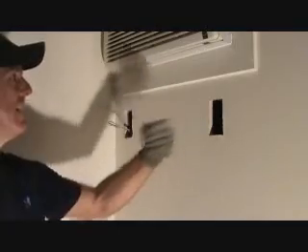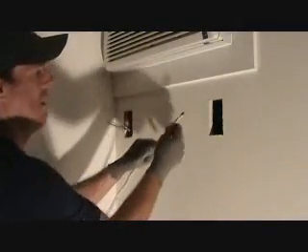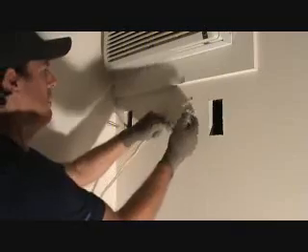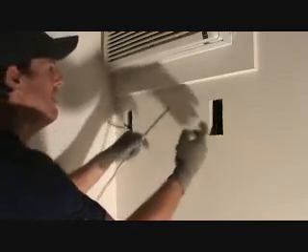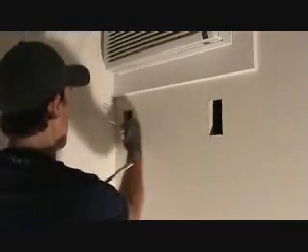So that means we got to put one wire through here and out. Then we got to take another wire from this box and go back over to here. So we're going to have two wires going through the hole in the stud. That's what I wanted to share with you, because if you drill a hole too small, you might think a half inch will do it — one wire, no problem. But we've got to get two wires through there. So I'm going to have two little pieces of wire shoved through this hole, fish that over to here, pull it out there. So we're going to have two wires going along here, two coming out here and two more coming out here along with the existing ones.